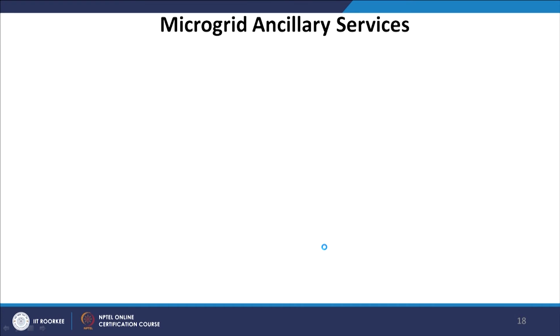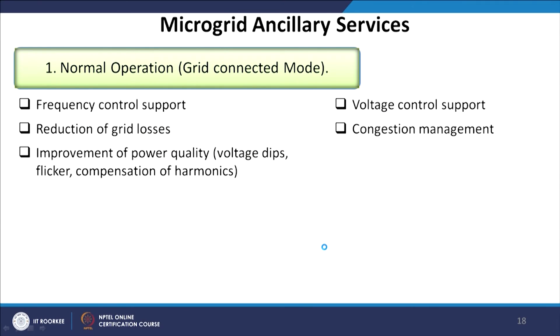One very important aspect is microgrid ancillary services — how a microgrid can help the system to have ancillary services such as frequency regulation. During normal operation in grid-connected mode, a microgrid can provide frequency control support, because frequency keeps changing based on load. A microgrid can support or complement frequency variation, is expected to reduce grid losses, improve power quality through compensation of harmonics, provide voltage control support, and finally provide congestion relief or management for low voltage networks.